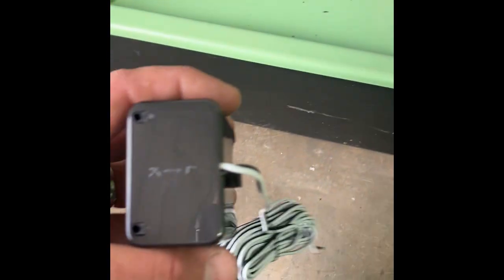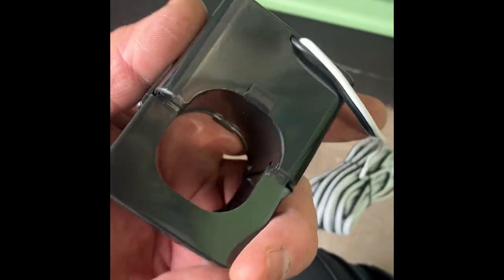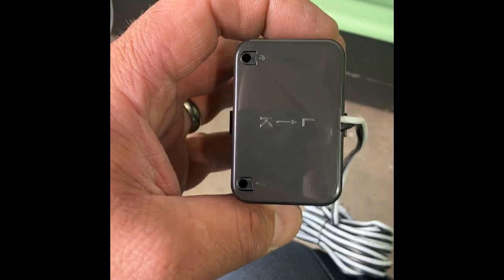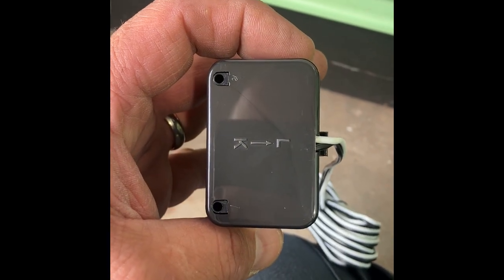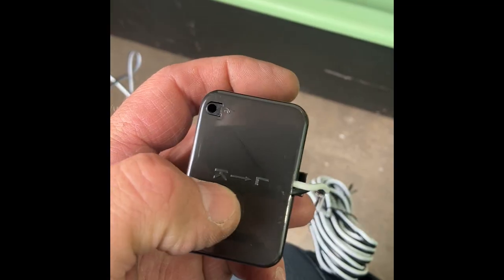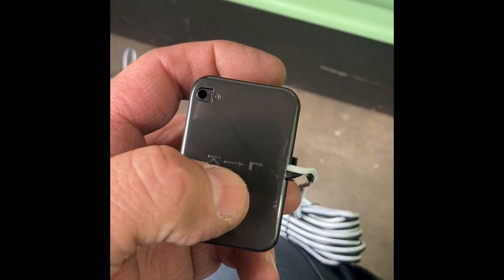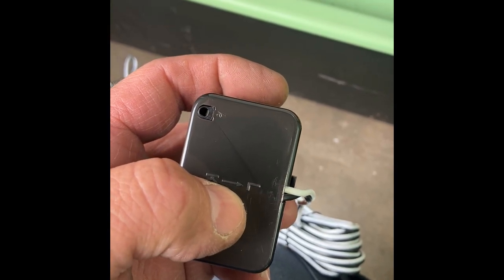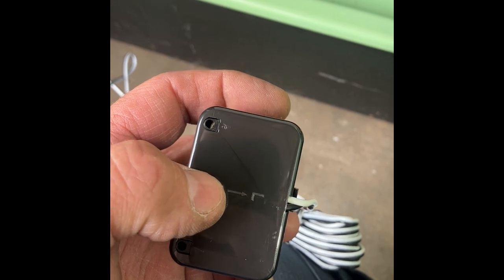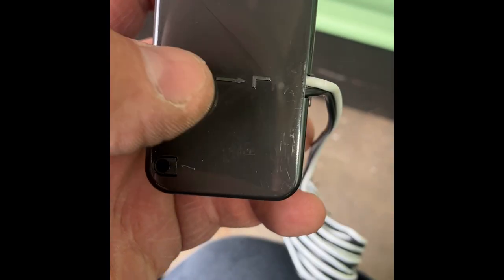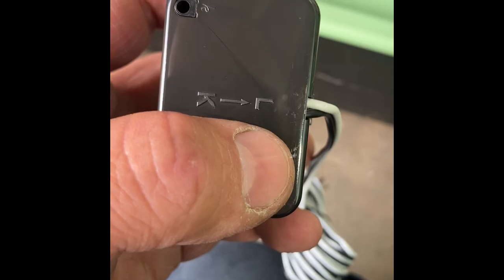Hey, just checking in real quick here, ladies and gentlemen. As I was installing these CTs, these just clip around the wires here to read your amperage. These are directional CTs, so when you install them you want to make sure current flows in the direction of the arrow.